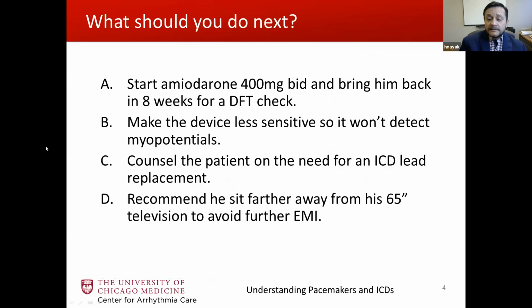So what would you do next? Your choices are: A, start amiodarone, 400 milligrams twice a day, and bring him back in 8 weeks for a DFT check. B, make the device less sensitive so it won't detect myopotentials. C, counsel the patient on the need for an ICD lead replacement. Or D, recommend he sit further away from a 65-inch television to avoid further EMI.